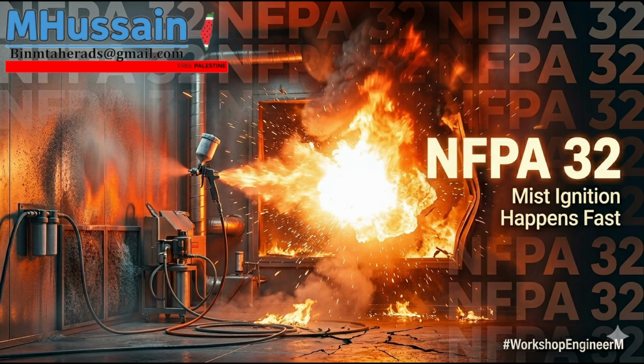Yes, the 2016 edition formally decoupled the rules. It states explicitly that requirements are less stringent for facilities that use higher classes of solvents, meaning higher flash points, less volatile, and newer equipment with built-in autonomous fire protection features. So if I specify version 4 equipment, which is highly automated, fully closed loop, and designed specifically for a safer solvent class, the code allows me to strip away those secondary architectural protections.